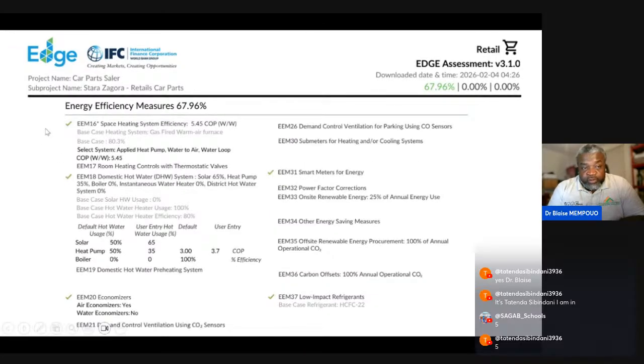One additional measure: because in Bulgaria we need both heating and cooling, space heating was also selected. During the summer period we need cooling, and during winter we need space heating. And then I also selected domestic hot water. In this case we have a 65% solar thermal system integrated in the project. When solar energy is available, we use the solar system, but when the sun is off, the heat pump kicks in and provides hot water in the building. So around 65% of hot water needs are met by the solar system and the remaining 35% by the heat pump.